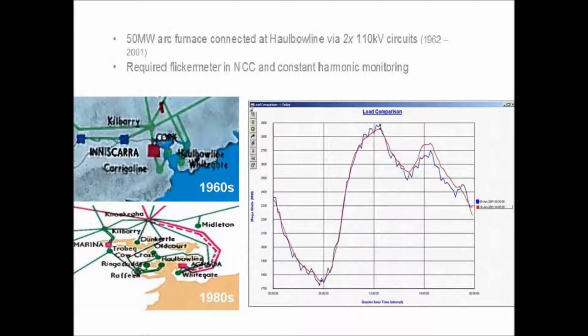In terms of harmonics, it was basically shunting out an awful lot of lower order harmonics. There were also problems with flicker, where the lights in Cork would flash on and off continually at around 8.8 hertz or thereabouts, so you'd have your lights on and off 8 times a second, which is pretty annoying. So there'd be constant monitoring of the flicker and the harmonics in the NCC itself. And if the flicker went above a certain value in the flicker meter, they'd be on the phone to Irish Steel to try and get them to sort it.